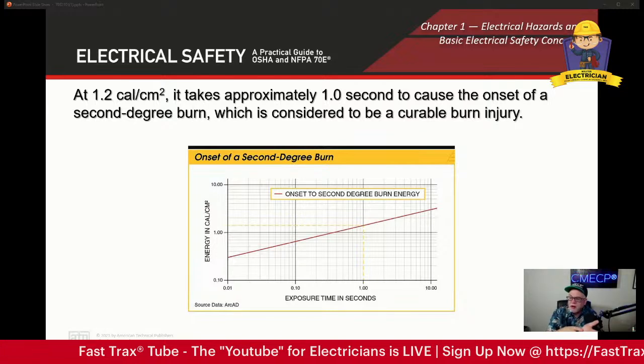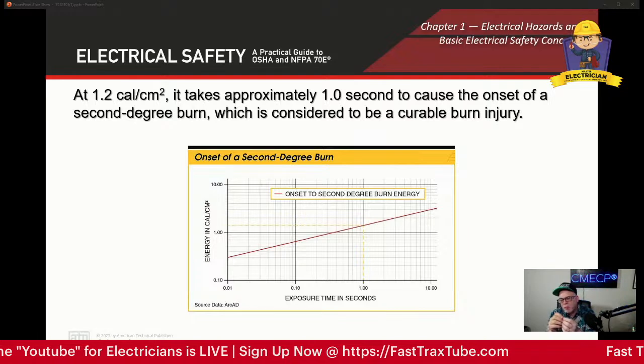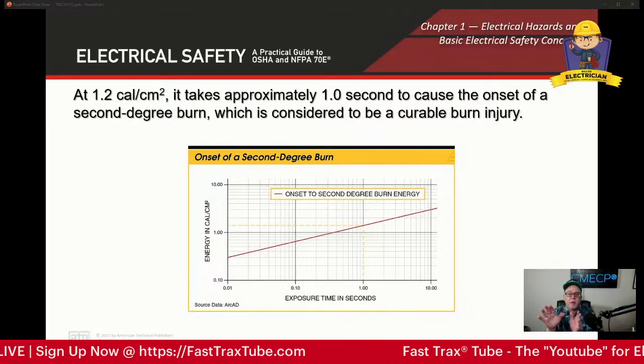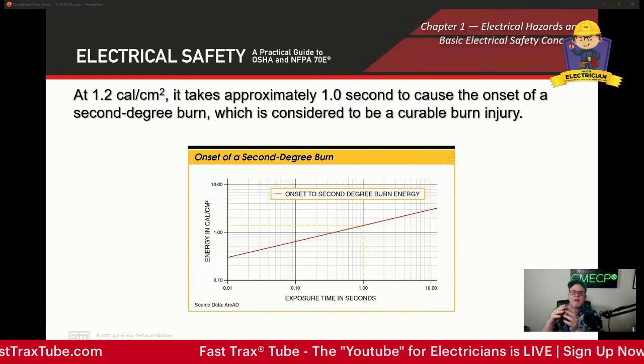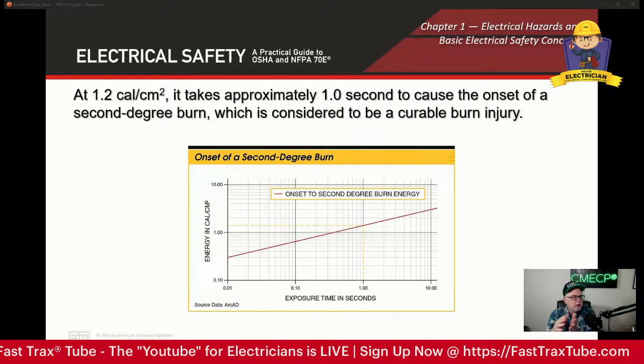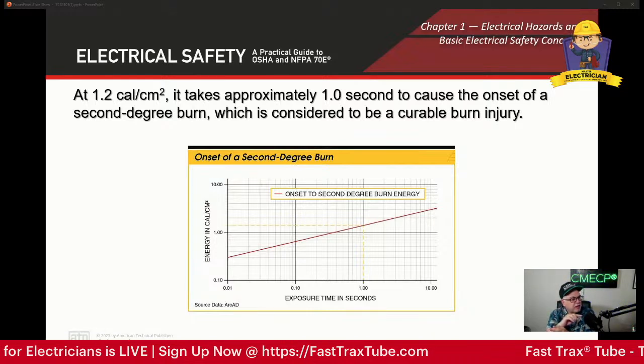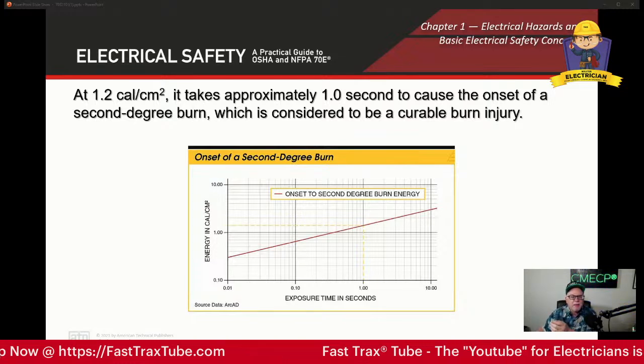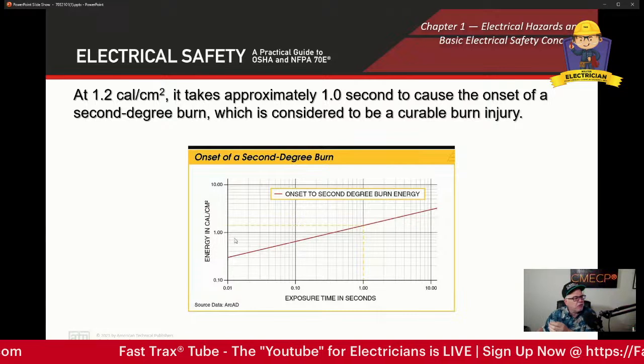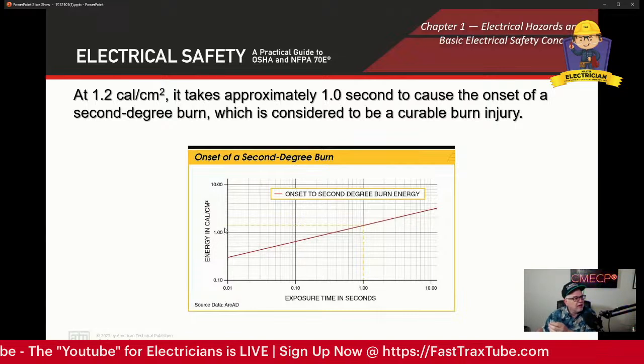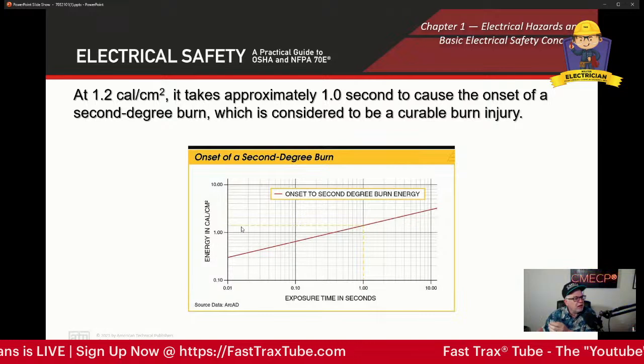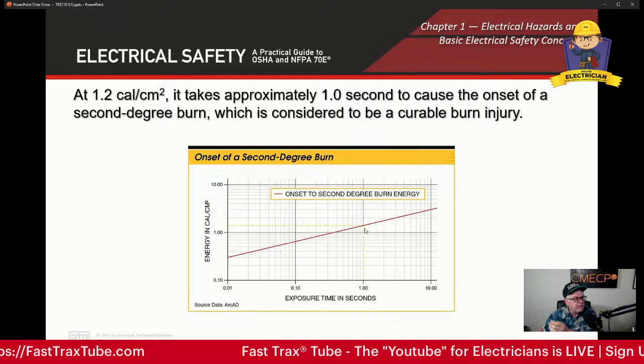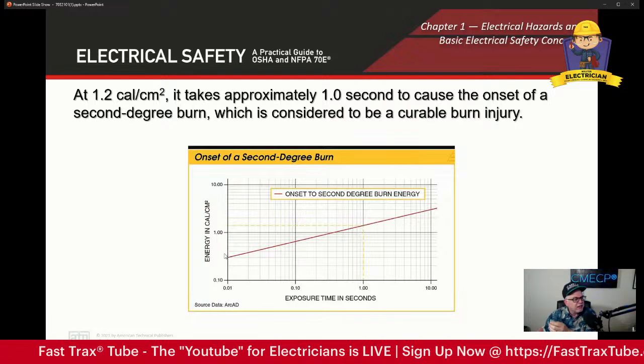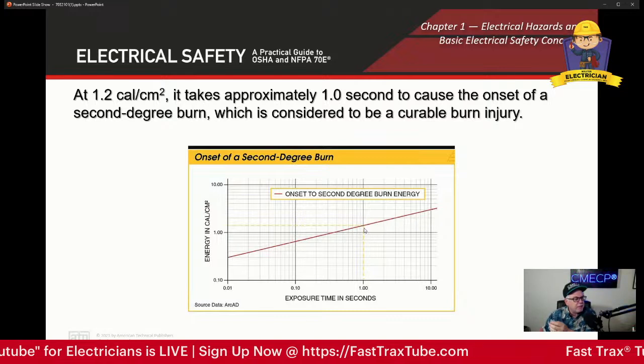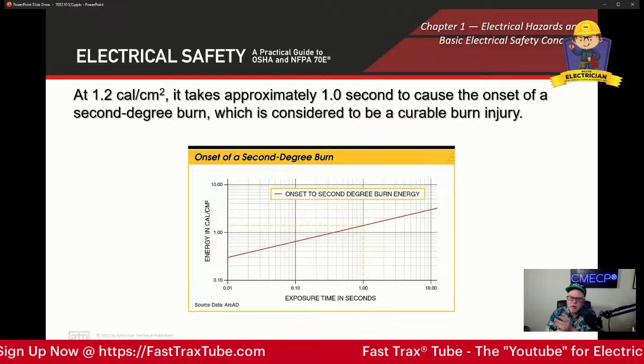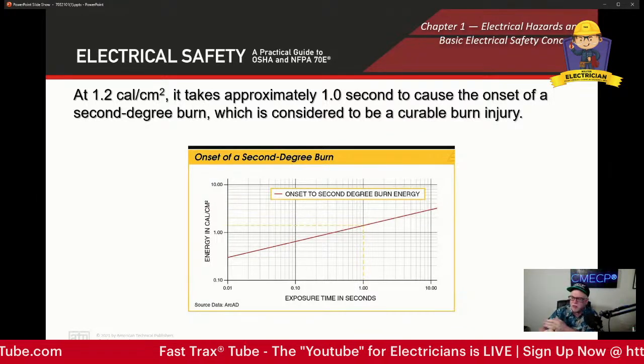Large areas of blistering increase the likelihood of infection. The small blistering you might get from this type of exposure for 1 second is considered survivable, and we're going to talk about why the calorie suits go much higher than this. If you look at the exposure in seconds as it goes up the scale, you can hardly see it. But right here with my mouse, the energy is at about 1.2, just above the 1, and it comes over here at 1 second. That's about where 1.2 calories per centimeter squared is, and you're going to receive curable second-degree burns.